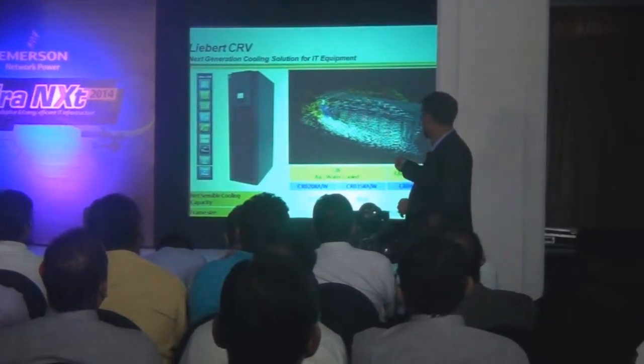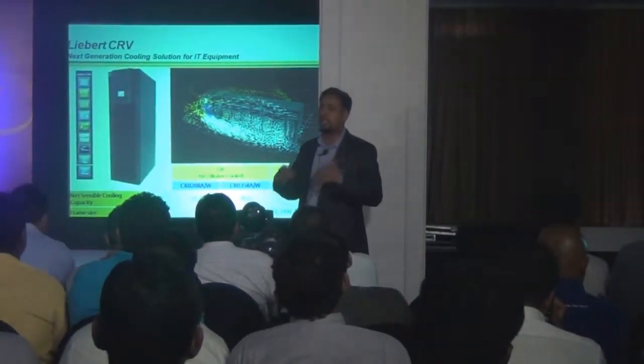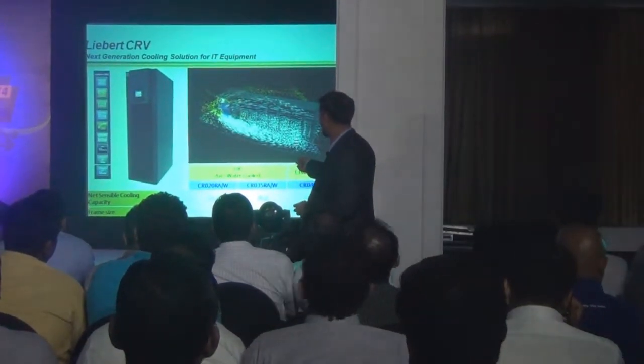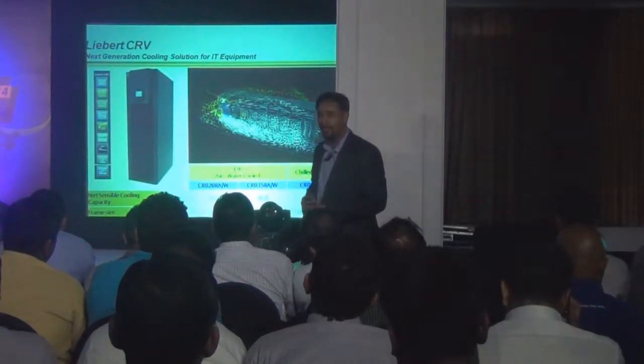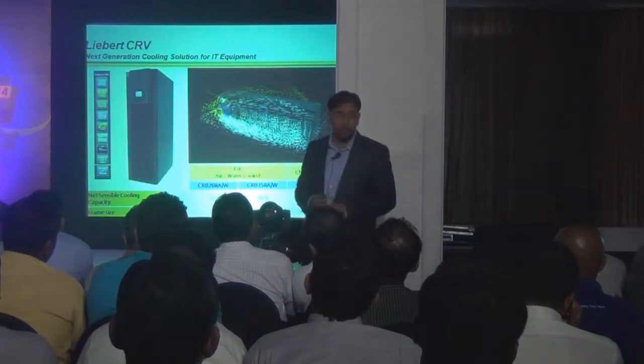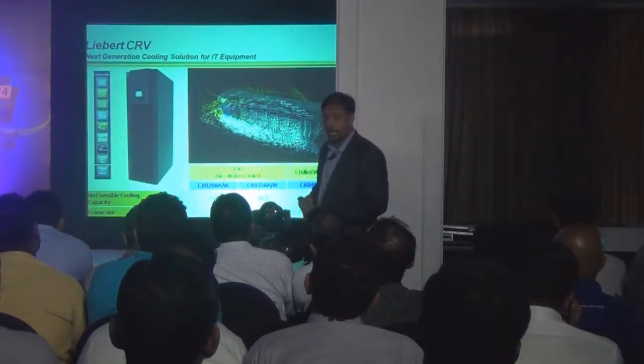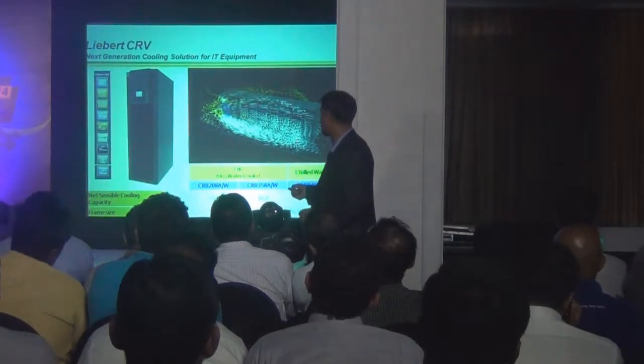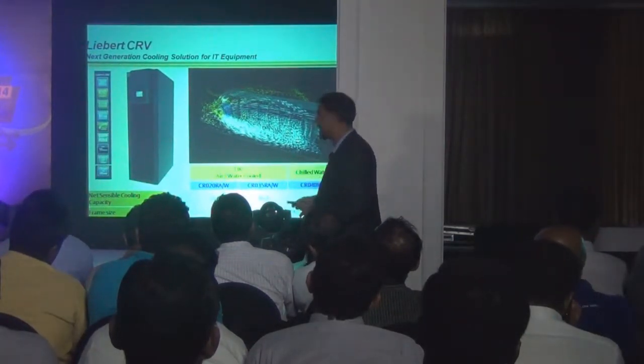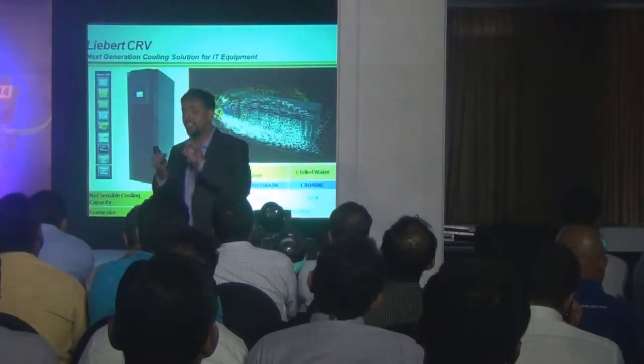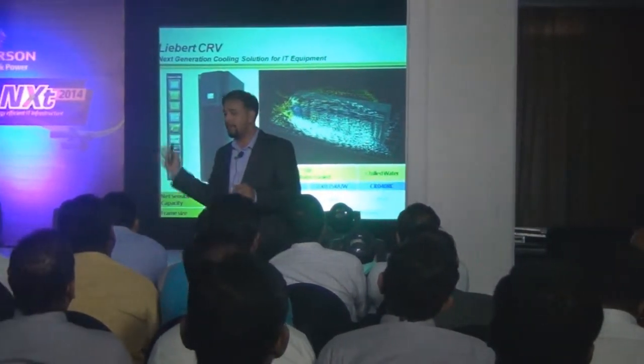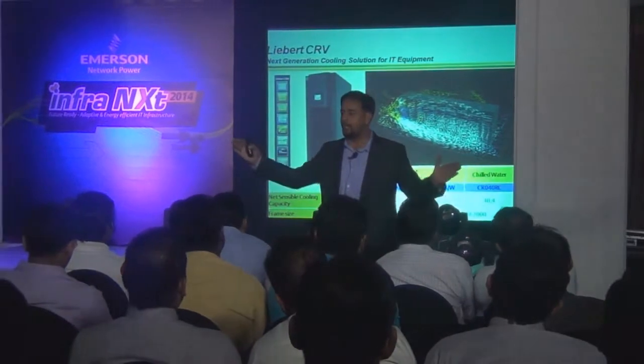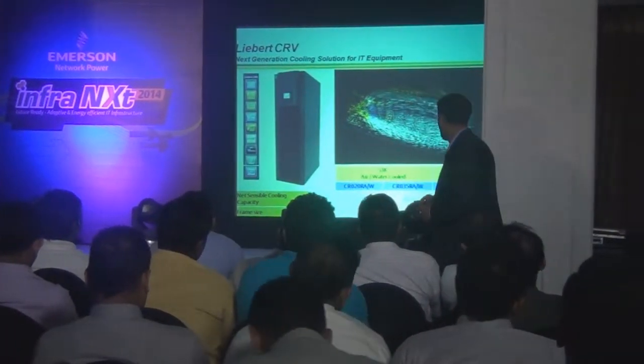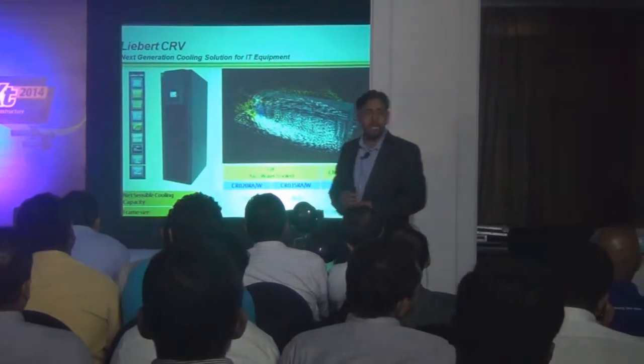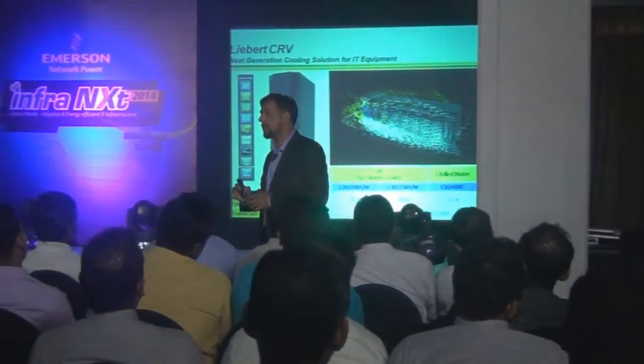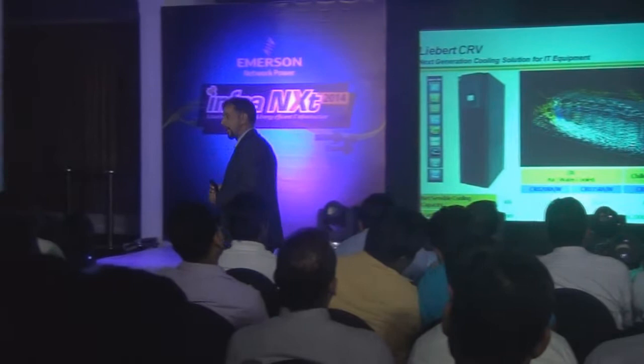This is how the system works. It is installed at the row level of the rack. That's why it is called a row cooling system as well. So it is throwing cold air in the front and sucking hot air from the back side. Okay, it can cool up to 20 kilowatt per rack with containment. We do cold air containment with the integration I just discussed in the last few slides. It is available with 410A gas, with digital scroll, EC fan and an outside variable condenser to give you maximum flexibility on the loading pattern side. And this system is typically 30 to 40% more efficient compared to the normal systems available in the market.